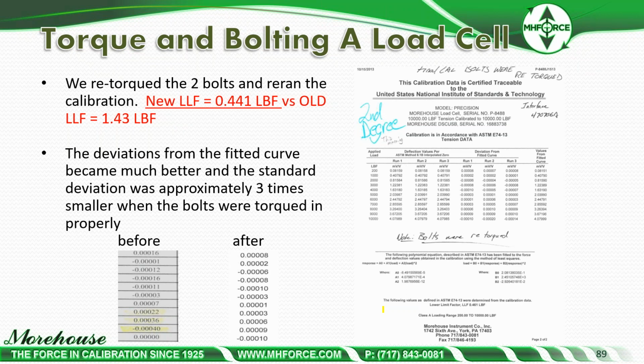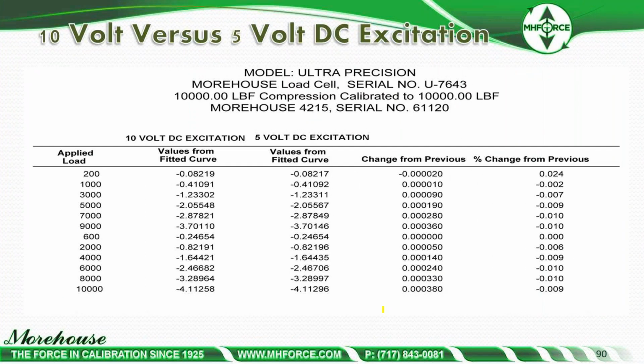So that's what happened. The deviations after were much less, and it's just one of those things that if you're bolting and unbolting cells, you have a lot more to worry about than just the calibration. You have to worry about R&R between your technicians. You need to worry about the difference in torque values. Most of those wrenches are 4% or better. So you have a lot of variation in that process.